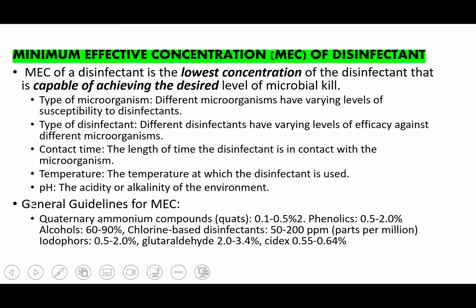The acidity or alkalinity, the pH, also determines the MEC of an agent. There's a general guide used for quaternary ammonium compounds, quats. The minimum concentration is between 0.1 and 0.5% for quats, for phenolic agents 0.5 to 2.0%, for alcohol 60 to 90%, for chlorine-based disinfectants 50 to 200 parts per million. Iodophors, glutaraldehyde, Cidex, they all have their minimums.